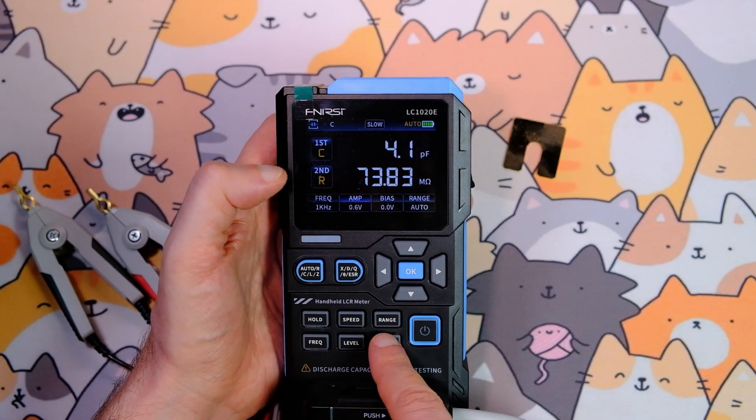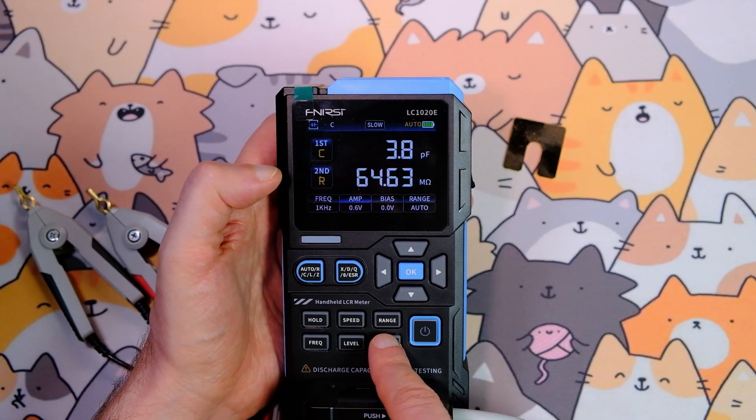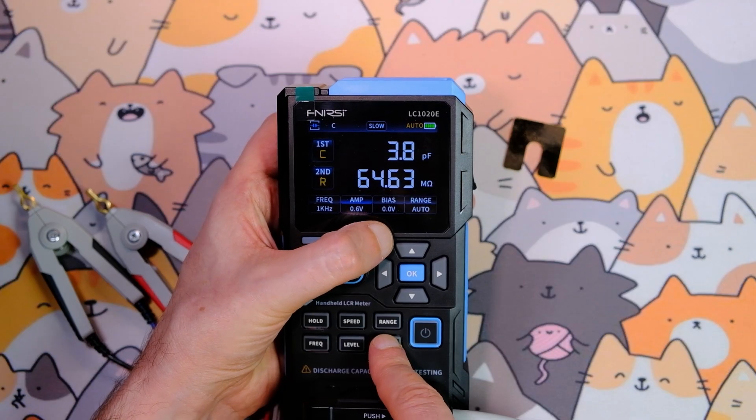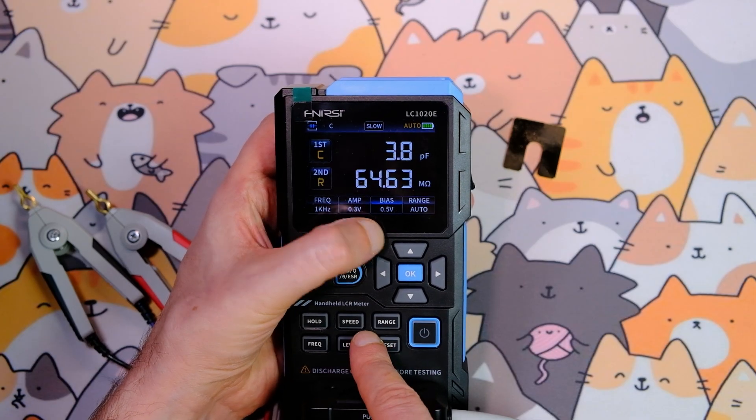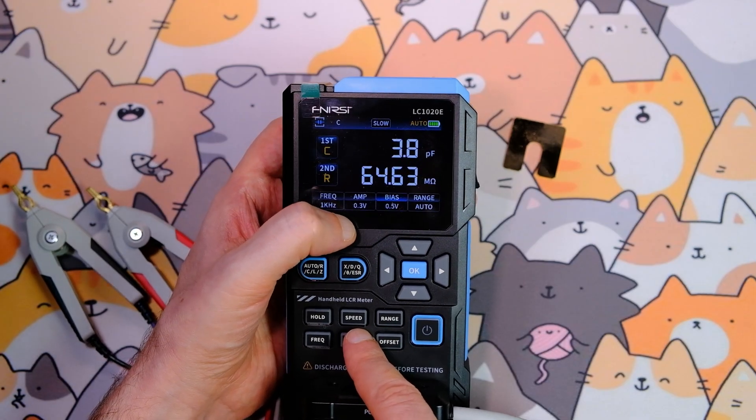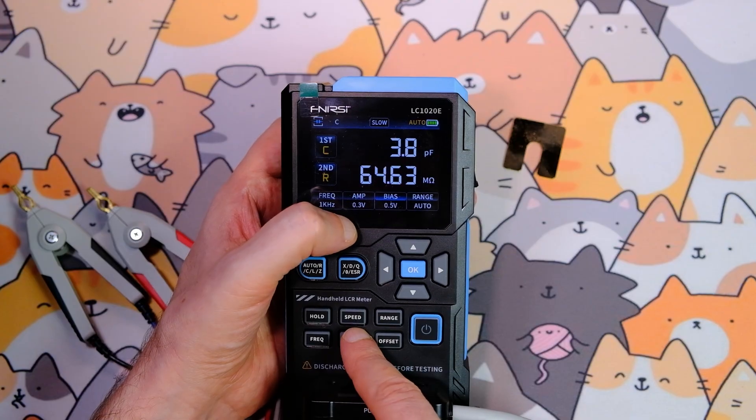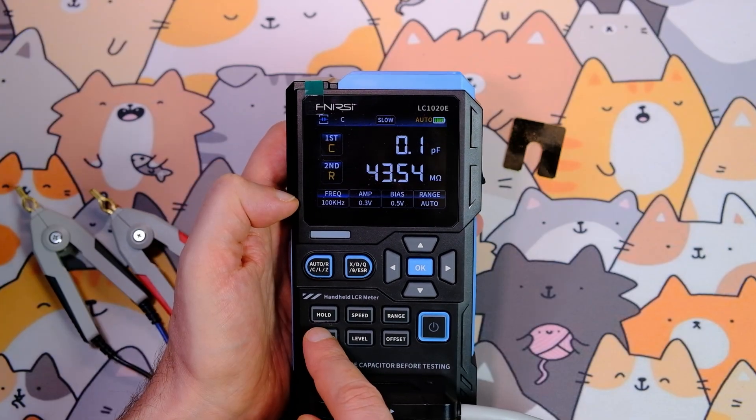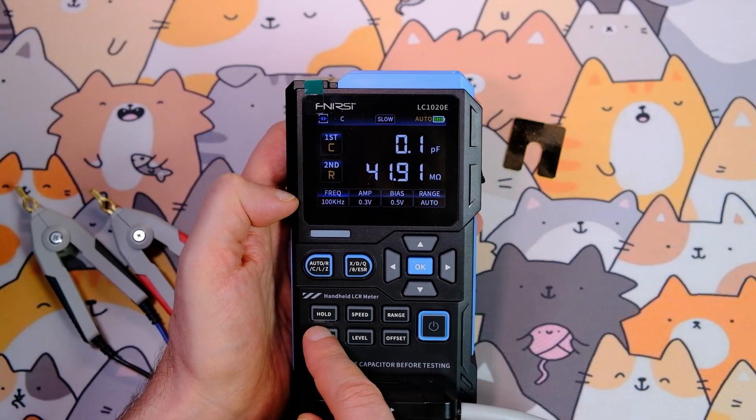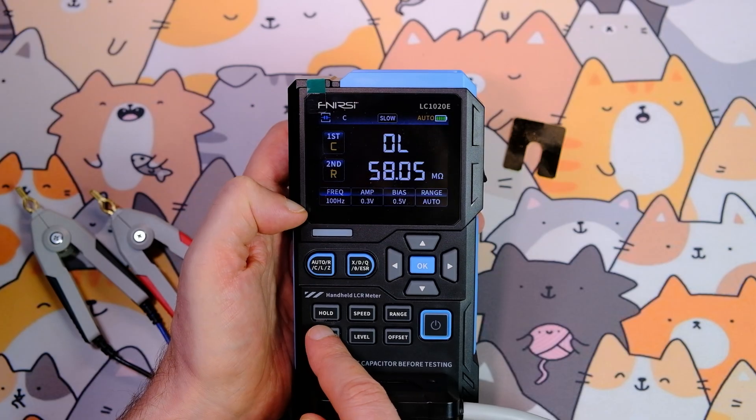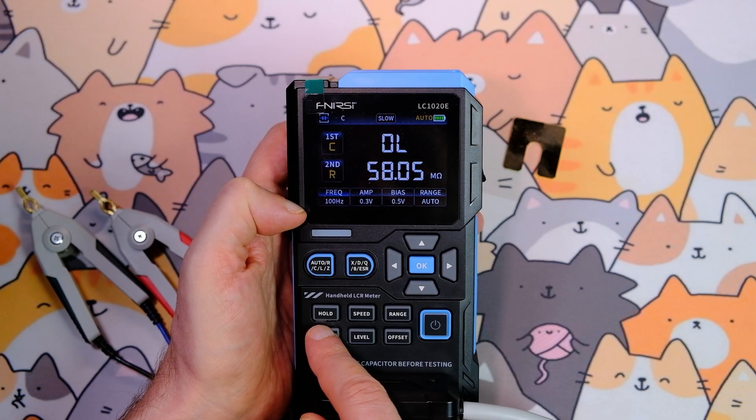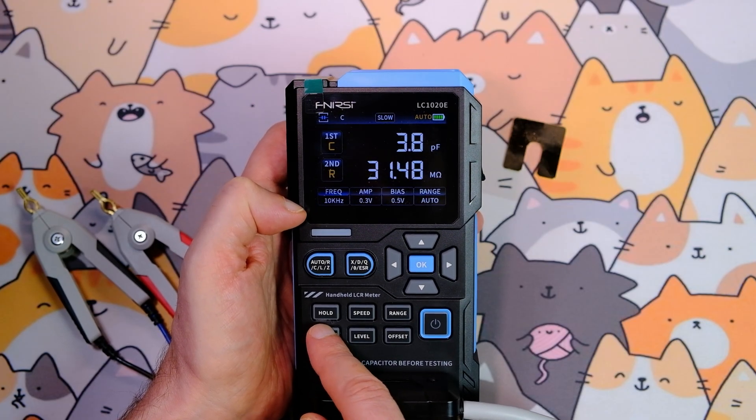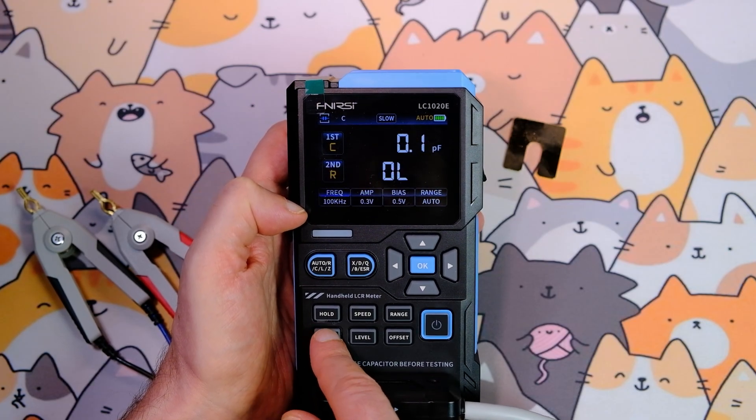Parameter measurements are performed via a bridge circuit using AC. The AC amplitude can be 0.1, 0.3, or 0.6 VRMS. Almost all measurements are recommended at 0.6 VRMS. You can also change the test signal frequency: 100 Hz, 120 Hz, 1 kHz, 10 kHz, and even 100 kHz.